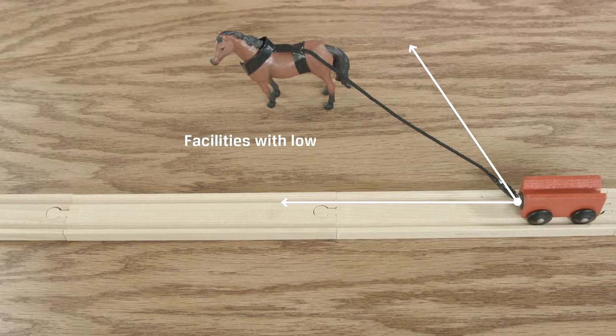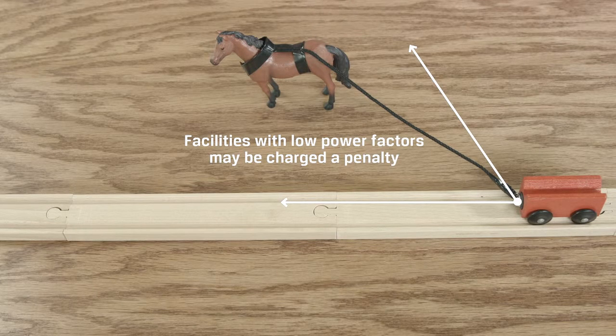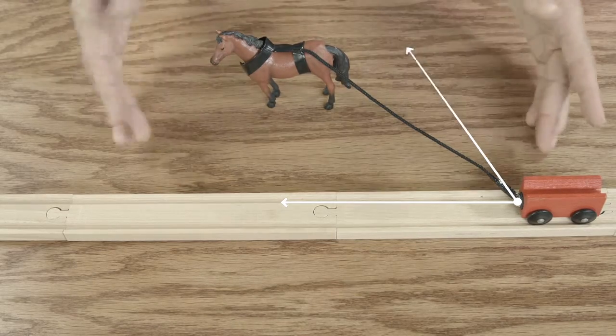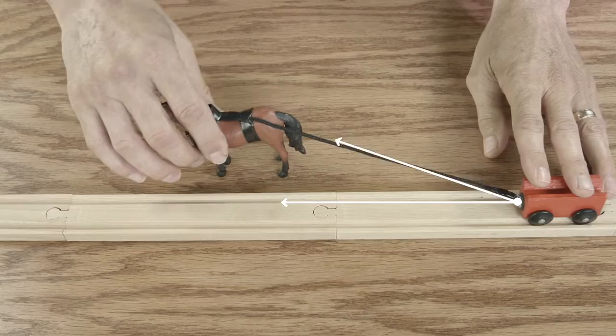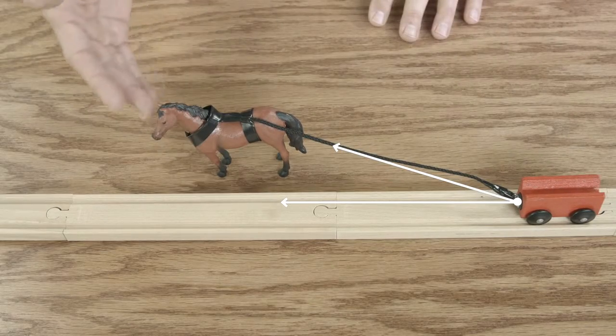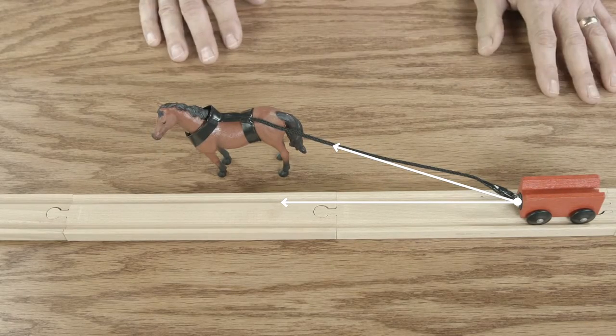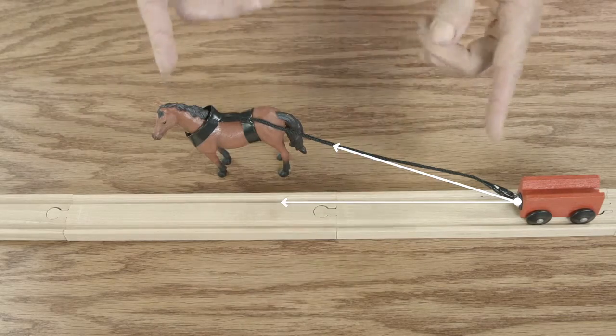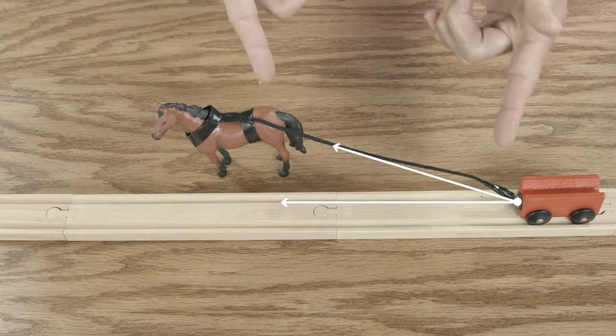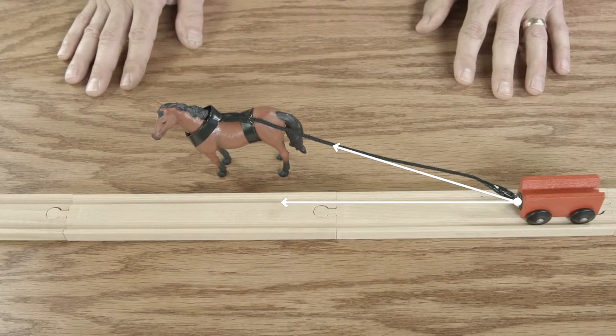If you have low power factor, you may be charged a penalty. This is because facilities with low power factor draw more apparent power, causing additional strain on the electric grid. To improve power factor, you have to reduce your reactive power. The best way to do that is adding capacitors to your electric circuit. When you reduce reactive power, you minimize the difference between real and apparent power, increasing your power factor.